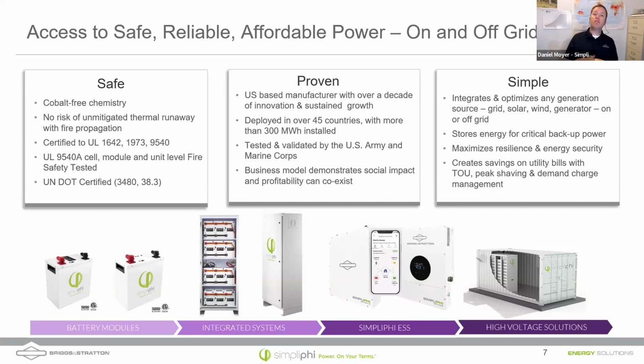So if you have an off-grid system with lead acid batteries, like some old Trojans or MK Deka batteries, we can swap those out for our lithium-ion batteries. All you have to do is get into your MagnaSine, your Schneider, your Victron, and adjust the set points in that charge controller or inverter to treat our batteries correctly. That's usually adjusting the float voltage, disabling the equalize function, adjusting the bulk, and setting that low battery cutout voltage, usually a little higher than what we'd see on lead acid batteries.